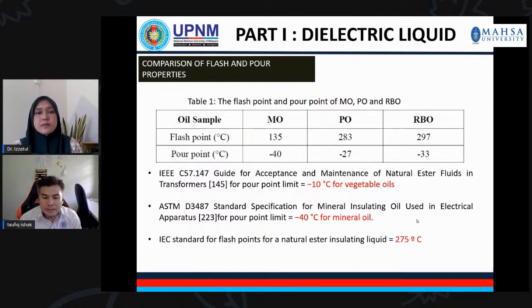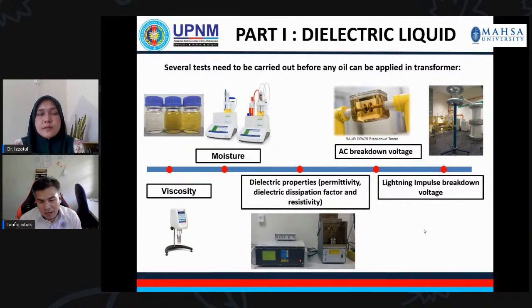In order to be used in the transformer, there are a few tests that need to be carried out. The first one, we need to investigate the viscosity of that particular liquid. The second one is to check how much moisture can be retained inside the oil. The third one is the common dielectric properties, including the permittivity, dielectric dissipation factor, and also the resistivity. This is a common test for any kind of insulation material. And the two most important parts are that you must comply with the AC breakdown voltage and also the lightning impulse voltage before you can use it inside the transformer, and before you can apply it to the industry.